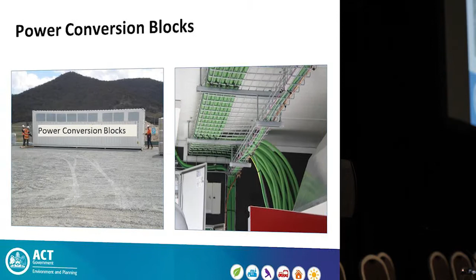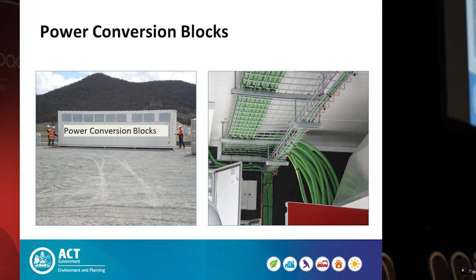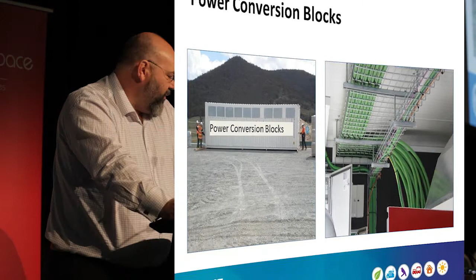So what you see there on the left is a power conversion block. On the right-hand end you'll get 24 1,000 volt DC cables coming in. They go into an inverter that consumes about half of it, and the other side is an 11 kV transformer. When it arrived on site, if you open it up and look at the right, there's something that's obviously not quite accurate - those are the mains cables on the 11,000 volt side.